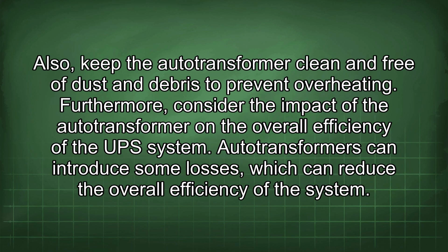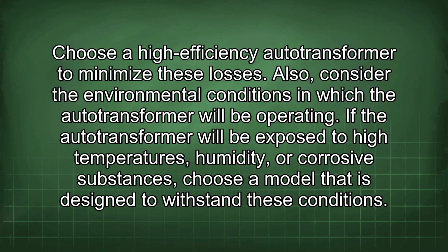Also, keep the autotransformer clean and free of dust and debris to prevent overheating. Furthermore, consider the impact of the autotransformer on the overall efficiency of the UPS system. Autotransformers can introduce some losses, which can reduce the overall efficiency of the system. Choose a high-efficiency autotransformer to minimize these losses. Also, consider the environmental conditions in which the autotransformer will be operating. If the autotransformer will be exposed to high temperatures, humidity, or corrosive substances, choose a model that is designed to withstand these conditions.